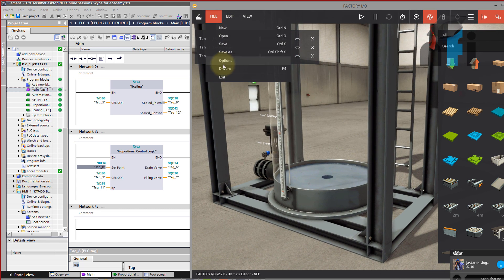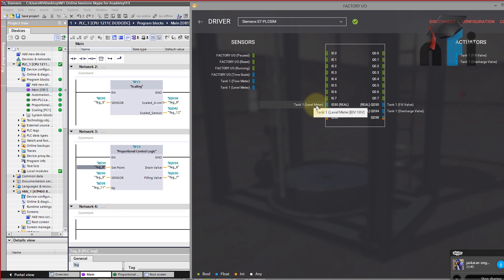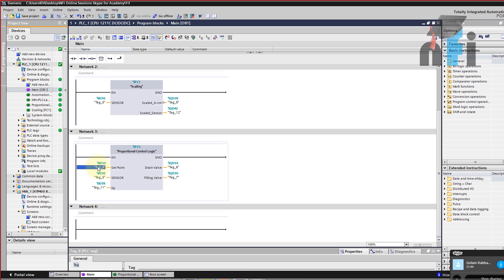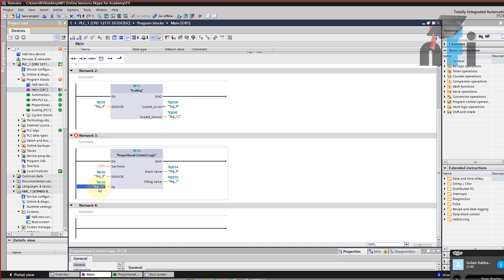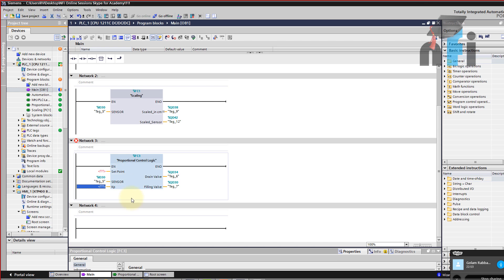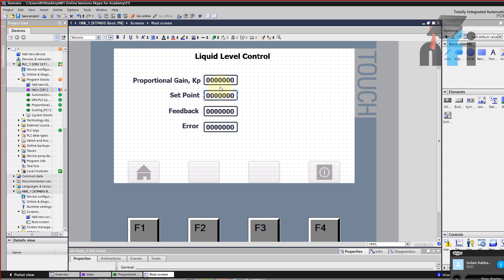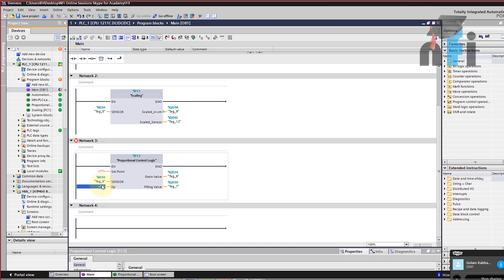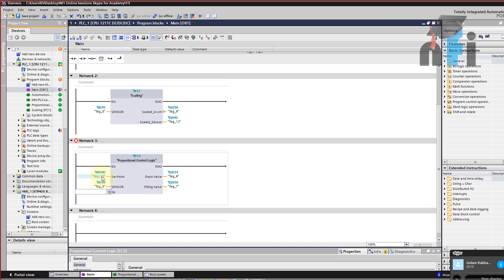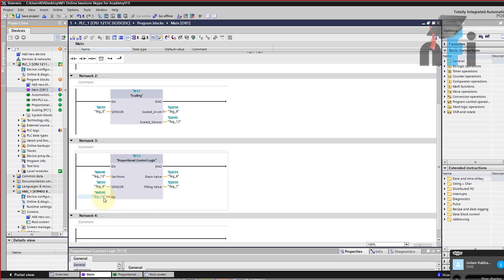In the proportional control logic, the address ID 34 was the set point coming from the panel. Since we are replacing the panel, we no longer need ID 34. I'll go offline and remove those panel-driven addresses. Instead, for set point I'll assign data address MD 40 as a real value, and for KP I'll use MD 45. These two values will now come from the HMI. So the set point is MD 40 and KP is MD 45 — go to your HMI and link those addresses.